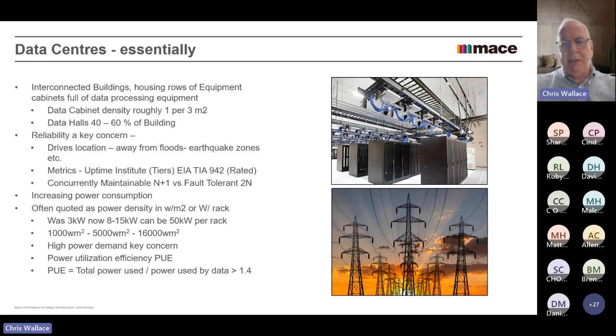And typically a PUE of 1.5, most people would not be satisfied with. Most people would only be satisfied with a 1.4 or below. Why I say that is a lot of people were trying to get down below 1.3, maybe into a 1.2, by using specialized chillers or something like that. But in many areas that we're dealing with now, water supply is not necessarily readily available, and they're going to go for an air-cooled chiller. And once you go for an air-cooled chiller, the efficiency drops, and obviously the power consumption goes up, and you may be up at a 1.4.